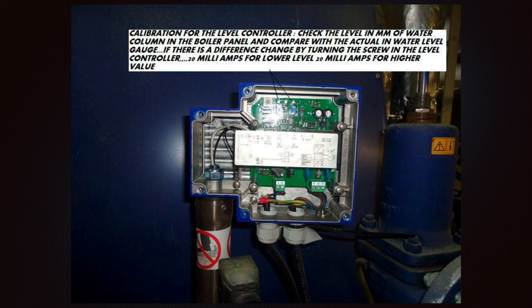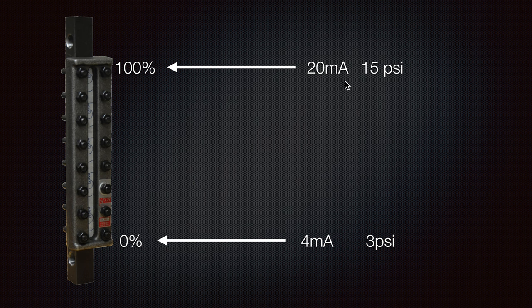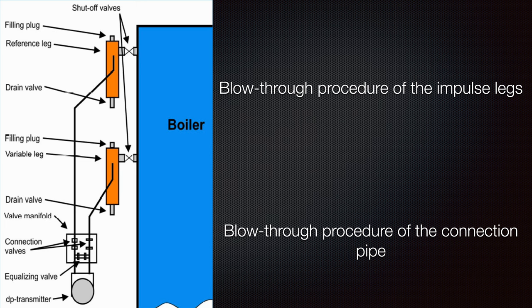Going back here: for the low level, the signal must be 4 mA — there appears to be a print mistake showing 20 mA. As we can see clearly, 4 mA corresponds to 3 psi in some cases where a pressure gauge is installed, and 20 mA corresponds to 100% at 15 psi. This gives a clear view of what 4 mA and 20 mA mean and the differences between 3 psi and 15 psi.